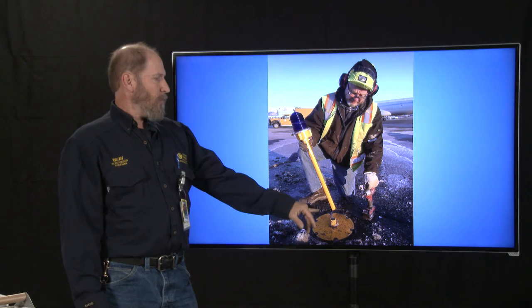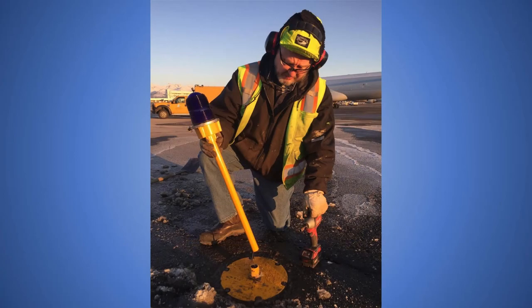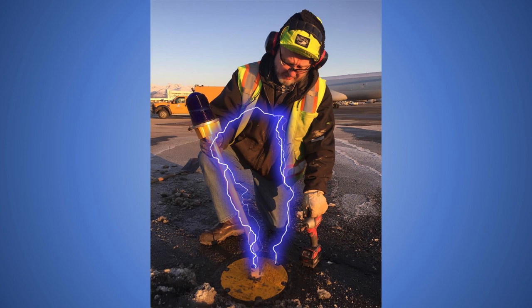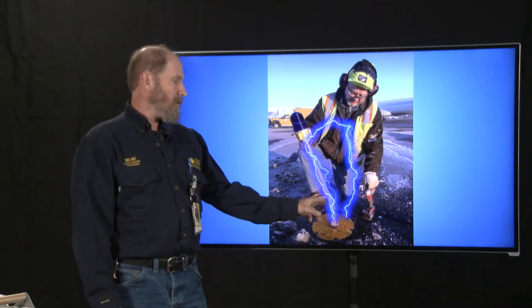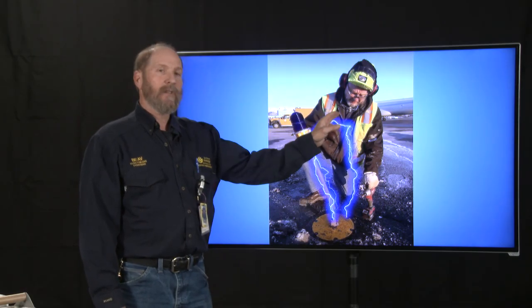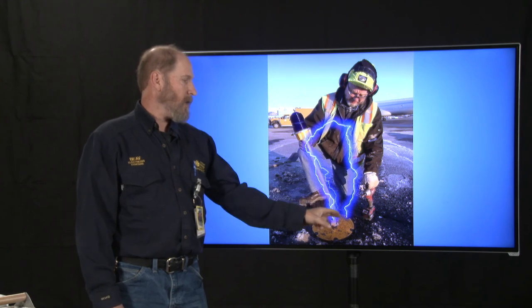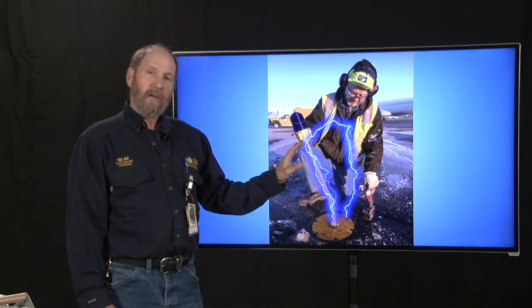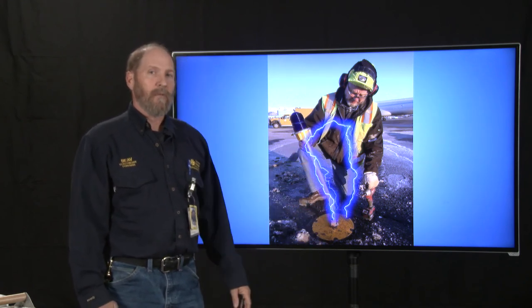what would happen if the electrician pulls that light out while it's still energized? Well, this is what would happen. It's going to still be seeking to get back to ground because you've disturbed that connection to ground. And it's going to go out of the electrician's, up the electrician's arm and out his knee and back to ground. And if this happens to you, it's probably going to be fatal.